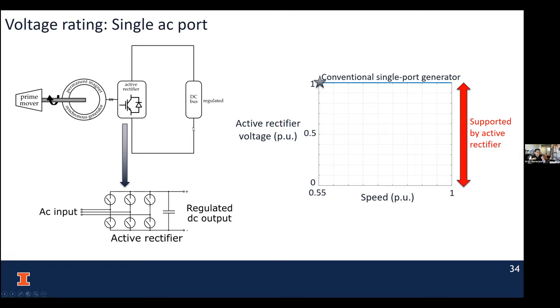Let's look at a single port machine. What do I mean by that? I have one three-phase output that connects to the active rectifier - this is the conventional system. This is option two, what we talked about. If I think about the voltage rating of this device, what do I have to deal with for this IGBT? Again, we're talking two level, so it's the same as the DC bus. It's independent of speed - the active rectifier voltage rating is determined by whatever the DC bus voltage is. Let's call it one per unit.